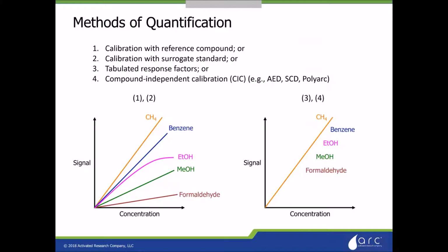The last method is compound-independent calibration, and that's where the detector has an intrinsically uniform response to a certain molecule or set of molecules. And this isn't a new concept. This was used in atomic emission detection, a very expensive detector, but it had a uniform response for each of the elements that it was looking for. The sulfur chemiluminescence detector converts everything to SO2, all the sulfur to SO2, and therefore you have a uniform response to sulfur. And now finally the polyarc for organic molecules. So what this does is it brings all of these molecules on a per carbon basis to the same response.